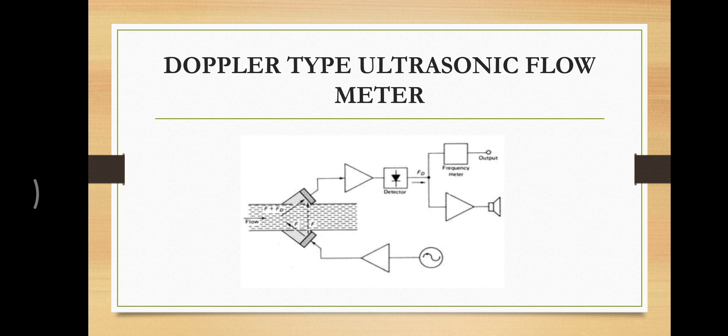Next one is a Doppler type ultrasonic flow meter. It consists of an oscillator which generates a frequency. This frequency is amplified by using amplifiers or drivers. This amplified frequency is sent to a transmitter and the frequency F is transmitted to receivers as F plus FD. It is sent to the amplifier and detected by the detectors.